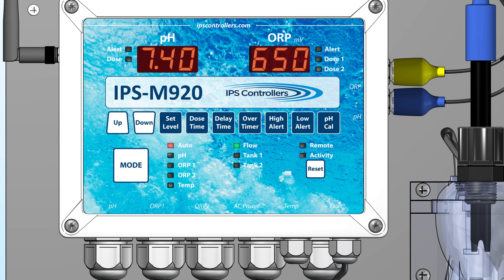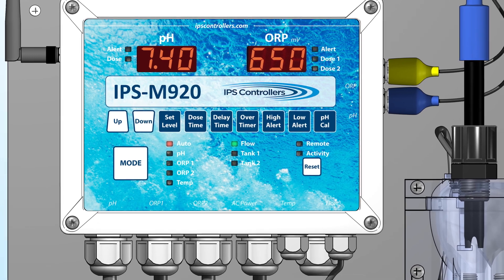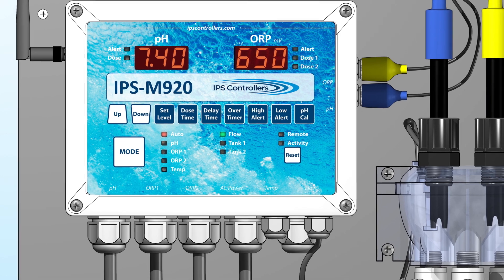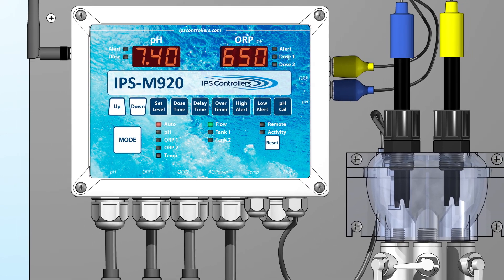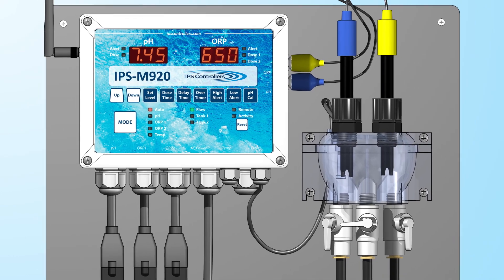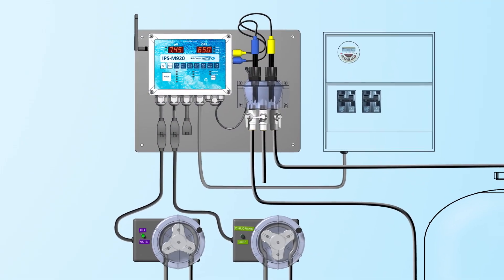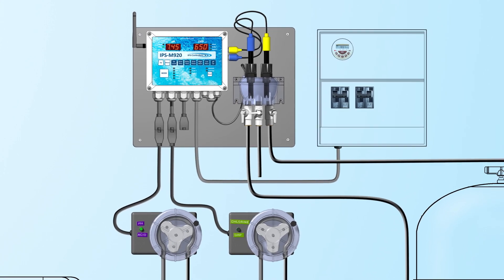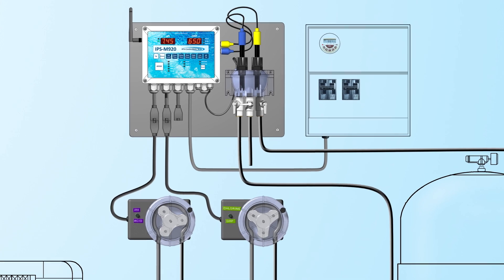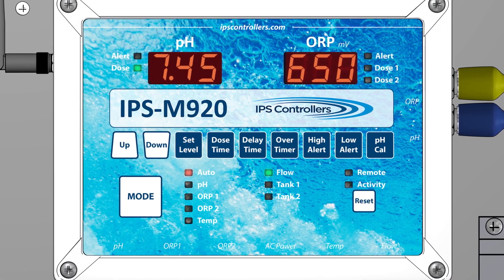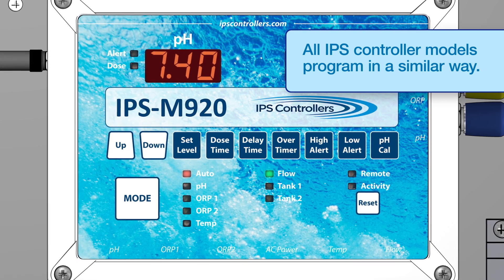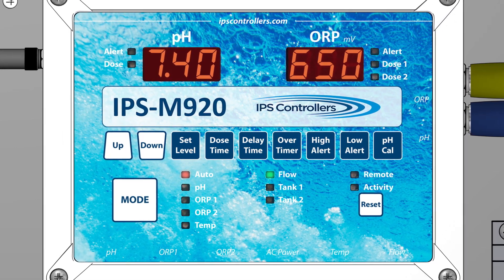The IPS controllers compare the readings received from the pH and the ORP sensors to the set levels programmed for pH, ORP1, and ORP2. If the readings are too high or too low, the controller will automatically turn on the chemical feed devices for the length of time that has been programmed for the dose time. The other settings are used to fine-tune the delivery of chemicals. The controller will also prevent chemical overdosing and underdosing.